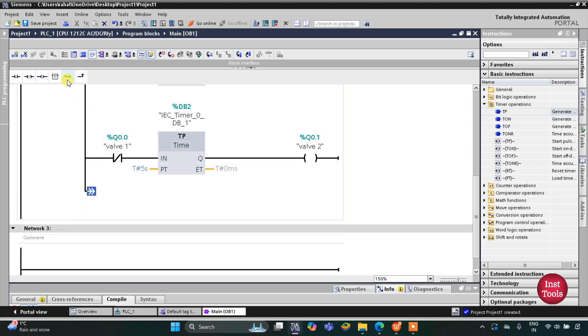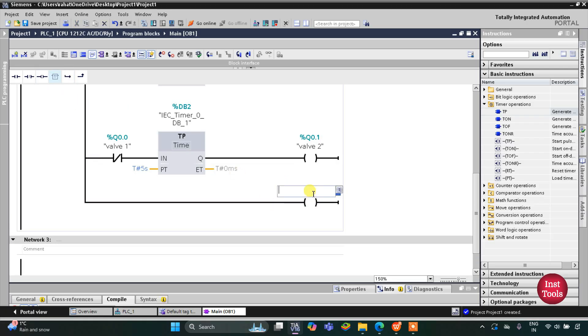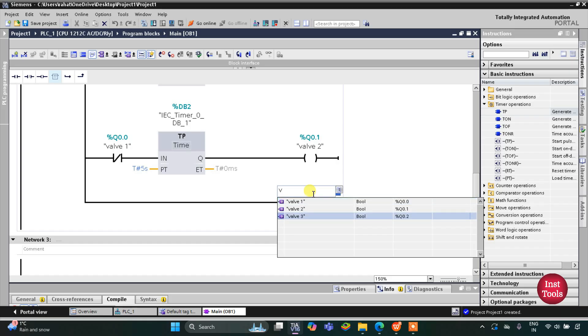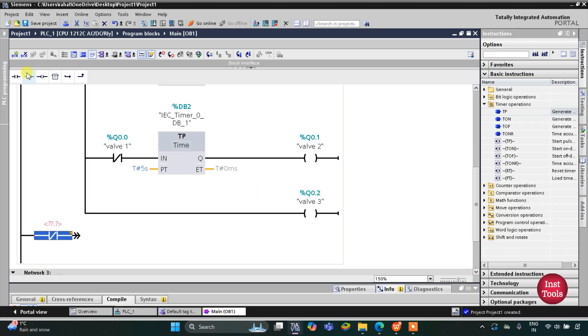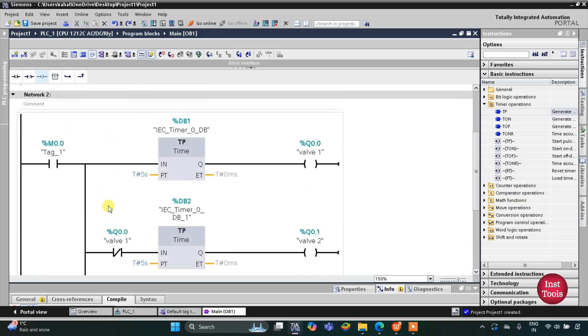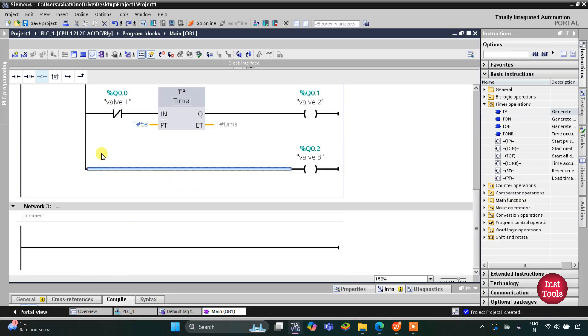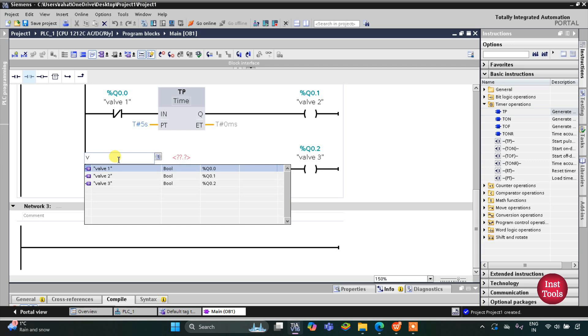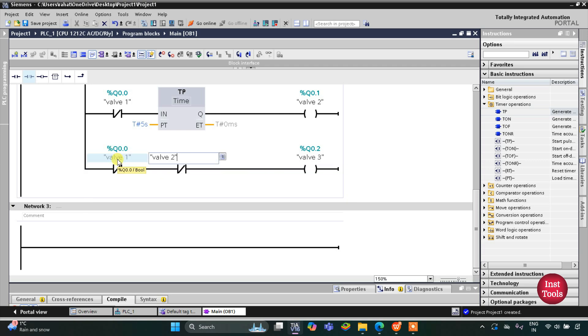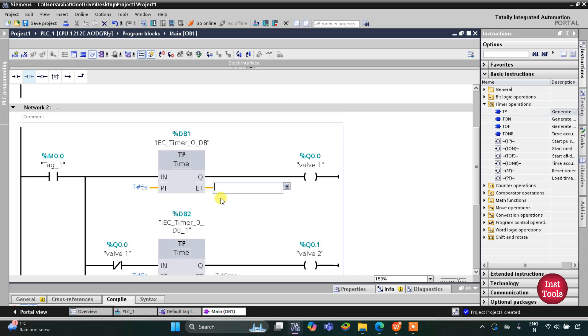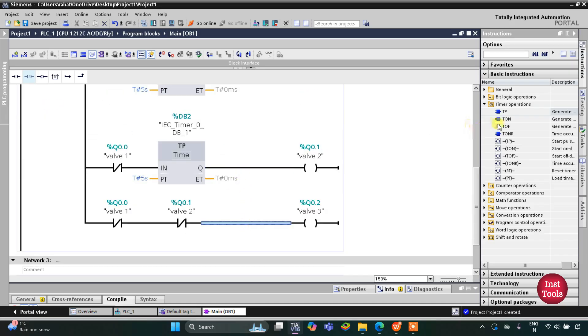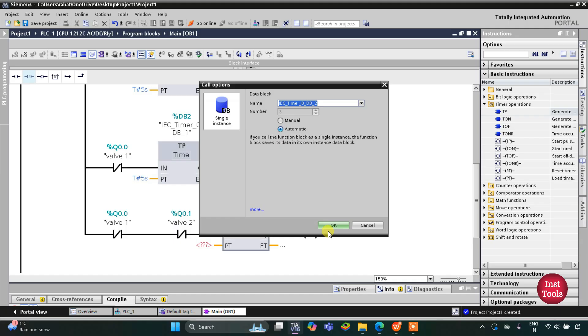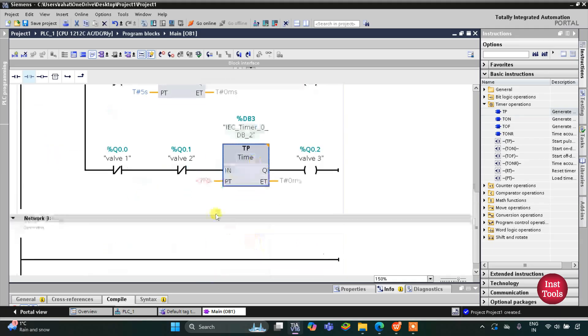I will open another branch and add a coil for Valve 3. Valve 3 will turn on when both Valve 1 and Valve 2 are closed, so I insert normally closed contacts representing Valve 1 and Valve 2. Valve 3 will also operate for five seconds using a TP timer with a preset value of five seconds.